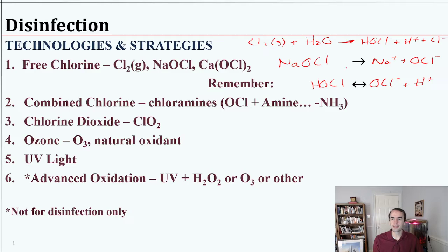So that's basically what our traditional or conventional chlorination does, is make use of specifically the HOCl. That's the stronger oxidant. It's a more powerful disinfectant. That's what we usually base our systems on, to try to use that molecule. Now, there's another molecule that occurs quite often, particularly in the presence of nitrogen. Nitrogen as ammonia, nitrogen even as nitrates or nitrites typically will get you there, but this type of chlorine is called chloramines or combined chlorine.